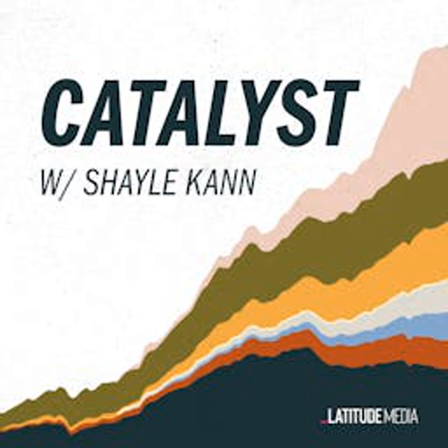I've been talking to these large owner operators of renewable power plants, and they have to send people out to measure what the oil health looks like and look at all the bushings and do all of these things to make sure that they don't have thermal events in the field. So they're a big pain point that people look to get rid of. So reliability is one, and you mentioned that. The other is the solution is about 1% absolute more efficient. That drives production value. And for battery installations, it's round trip efficiency improvement. So it doesn't just count once, it counts twice.